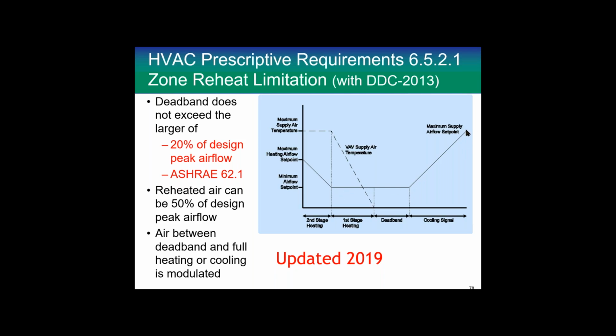So what happens is as the room cools down, you'll supply air, let's say at 55 degrees because that's standard, and your damper starts to close and gets down to the minimum set. Now your minimum set could be 20, or whatever you calculate at ASHRAE 62, but one of those numbers somewhere in there. This used to be 30 is what everybody would kind of set at, but we believe we can drive it down to 20. All right, and here's the second reason coming up.